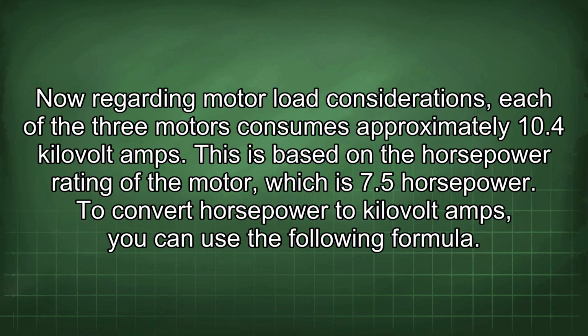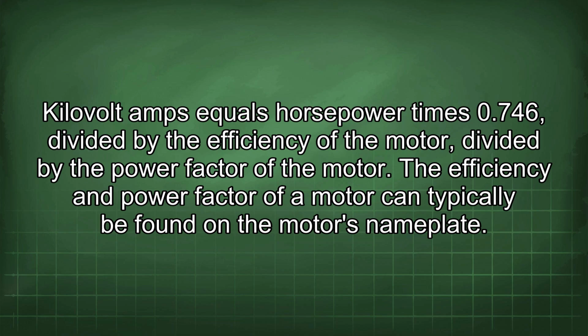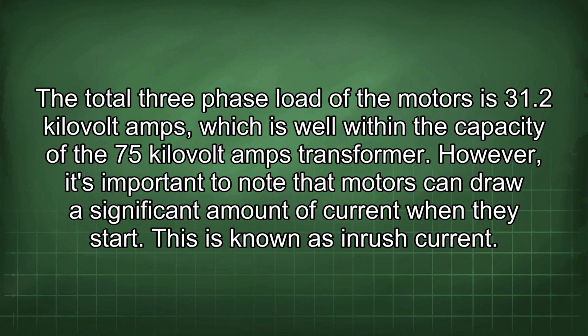Now, regarding motor load considerations, each of the three motors consumes approximately 10.4 kVA. This is based on the horsepower rating of the motor, which is 7.5 horsepower. To convert horsepower to kilovolt amps, you can use the following formula: kilovolt amps equals horsepower times 0.746 divided by the efficiency of the motor divided by the power factor of the motor. The efficiency and power factor of a motor can typically be found in the motor's nameplate.